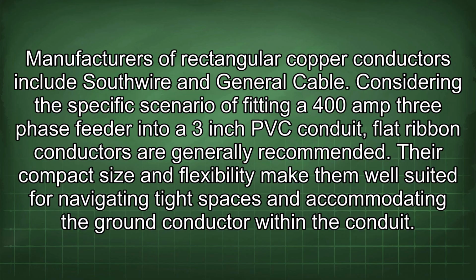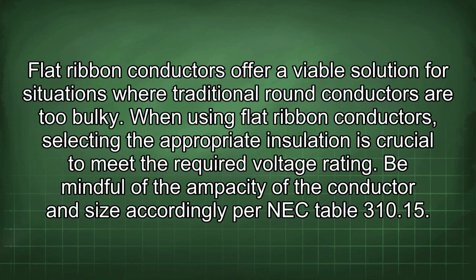Considering the specific scenario of fitting a 400 amp 3-phase feeder into a 3-inch PVC conduit, flat ribbon conductors are generally recommended. Their compact size and flexibility make them well suited for navigating tight spaces and accommodating the ground conductor within the conduit. Flat ribbon conductors offer a viable solution for situations where traditional round conductors are too bulky.